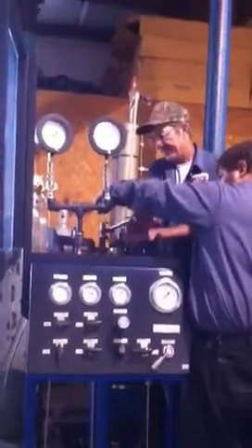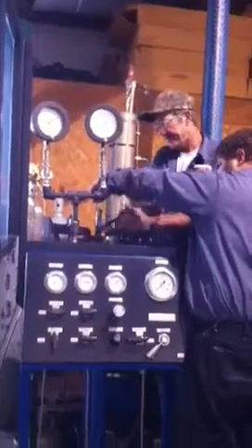We're tightening it down. I'm going to slide in here for a second — hold it up, Eric, before you close. I'm going to show them the two test gauges up here. We have two matched sets of test gauges that we test all the valves on.